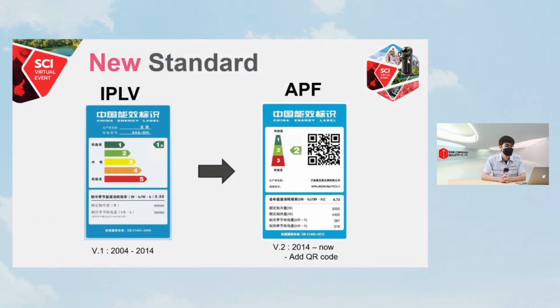Back in 2004 to 2014, China used the IPLV standard to declare the energy level. After that, it changed to the APF standard to declare the energy level. Comparing the two on the same air conditioner device, IPLV was level 1, but if we test for APF, you get only level 2. So if you want to get level 1 in APF, you need to do something in your unit. And we already did it for you with our compressor.